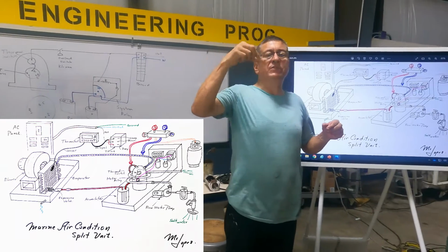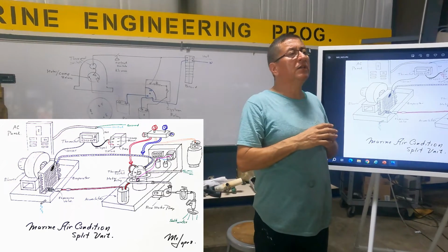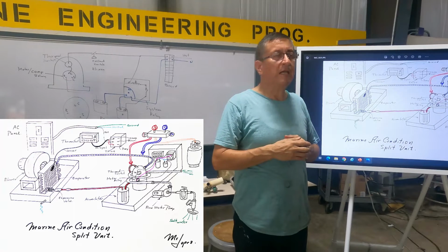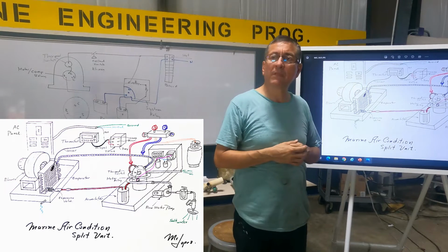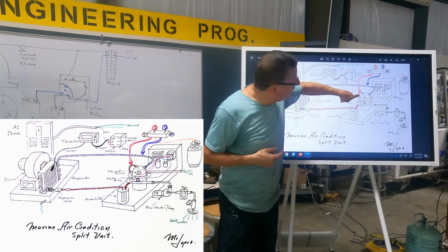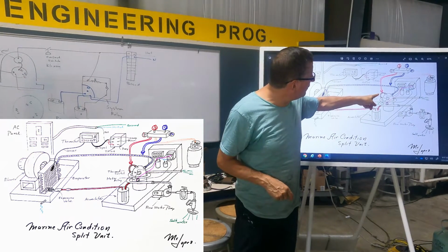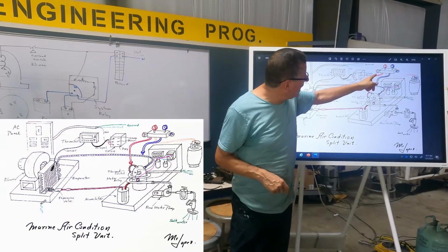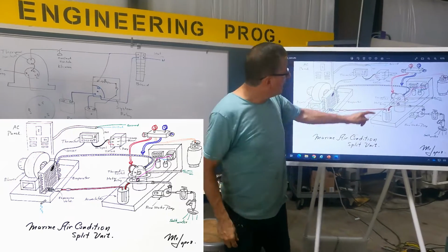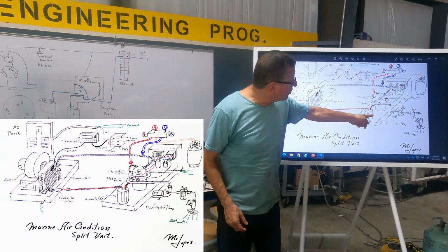The compressor has two pipes. One pipe is big and the other one is smaller. The smaller pipe is for high pressure, for discharge, and the big one is for suction. All right, the blue one. Ready, guys? Pay attention. Immediately, the gas goes out from the compressor at high pressure. You have the feeding for the gauge, and you also have another feeding for the high pressure switch. And immediately the high pressure line goes out and enters this accumulator.